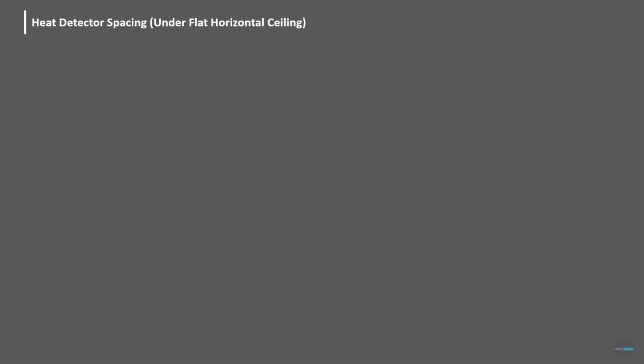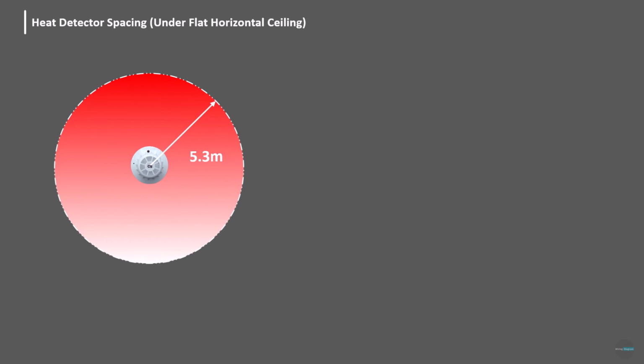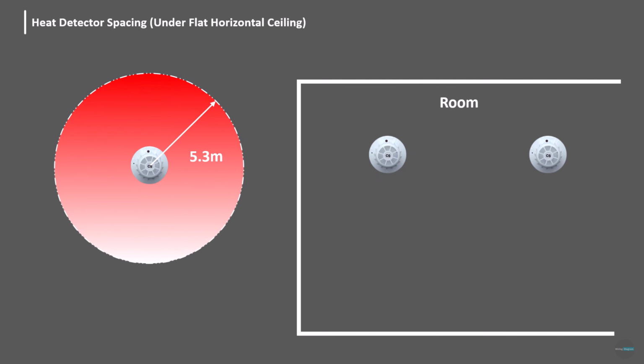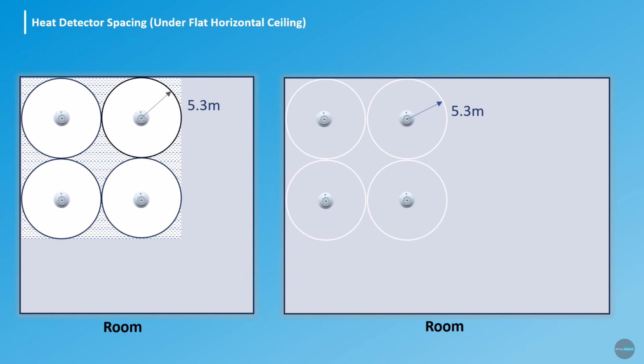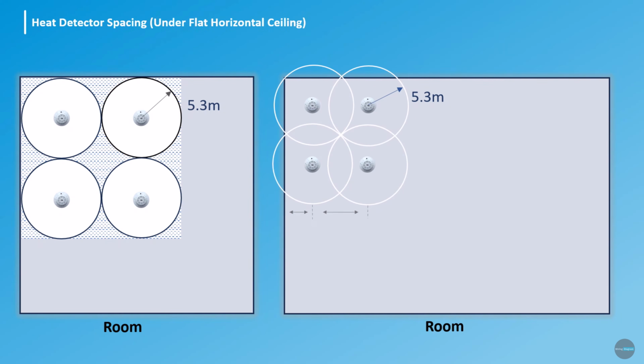Heat detector spacing at flat horizontal ceiling. Under a flat ceiling, one heat detector has an individual coverage radius of about 5.3 meters. But when we design a room or hall, the distance between two heat detectors is kept 7.5 meters and the distance from the wall is 3.8 meters. With this spacing, each heat detector covers a square area of 7.5 by 7.5 meters, which equals 56.3 square meters per detector. This arrangement ensures that the coverage areas overlap and no blind zones are left in the room.